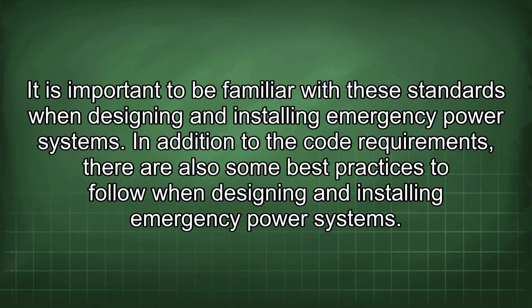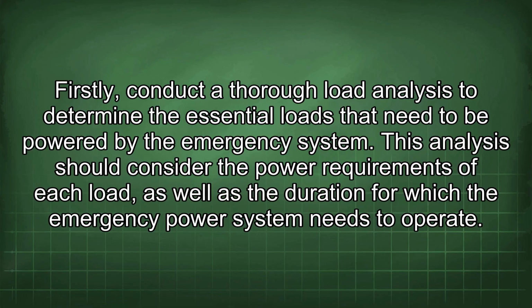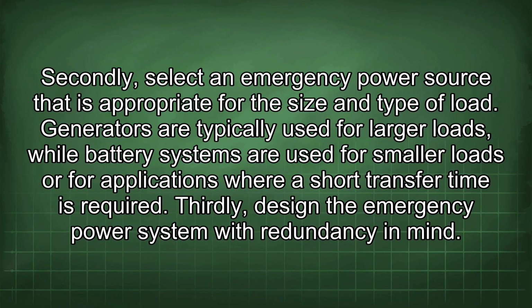In addition to the code requirements, there are also some best practices to follow when designing and installing emergency power systems. Firstly, conduct a thorough load analysis to determine the essential loads that need to be powered by the emergency system. This analysis should consider the power requirements of each load, as well as the duration for which the emergency power system needs to operate. Secondly, select an emergency power source that is appropriate for the size and type of load. Generators are typically used for larger loads, while battery systems are used for smaller loads or for applications where a short transfer time is required.